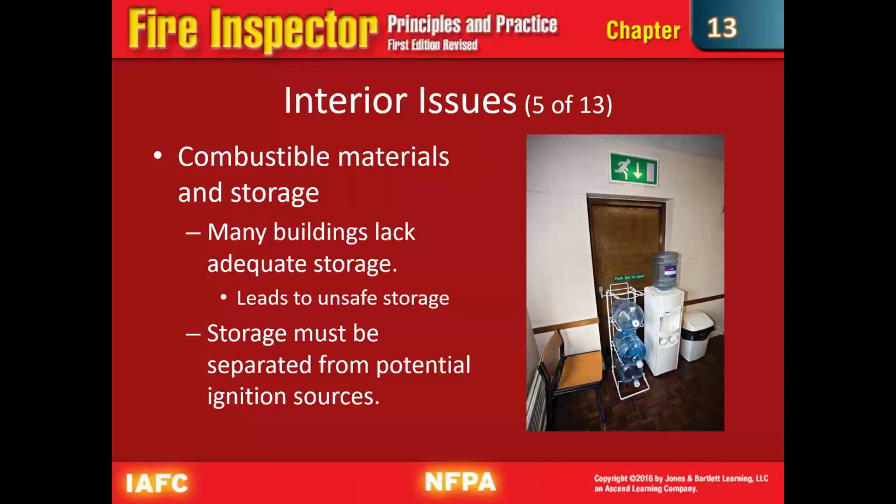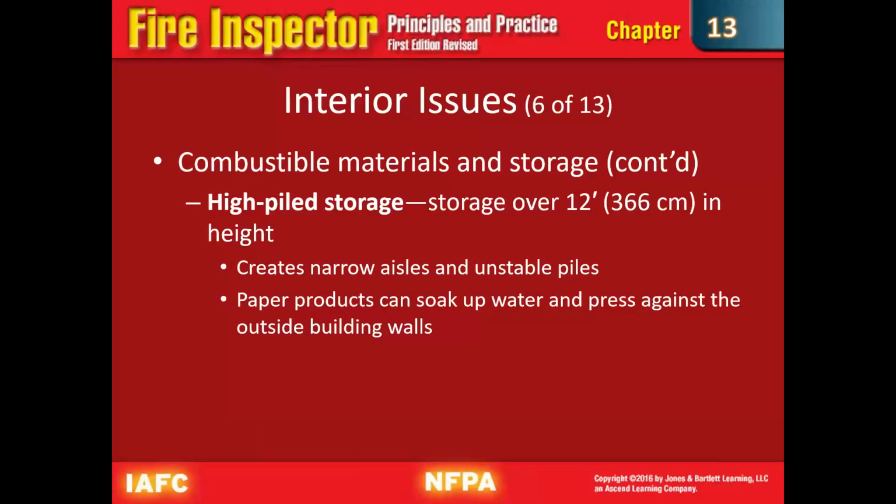You want to try to keep away any of the ignition sources, or as much of the ignition sources as possible. High piled storage is over 12 feet in height, and in some places they have narrow aisles and unstable piles. So these are things not only for the ignition hazard, but also the hazard for responding firefighters. If you're going in there and doing a search, and it's all these different materials stacked up, if it falls down on a firefighter trying to do a search in there, that's going to be a bad day.